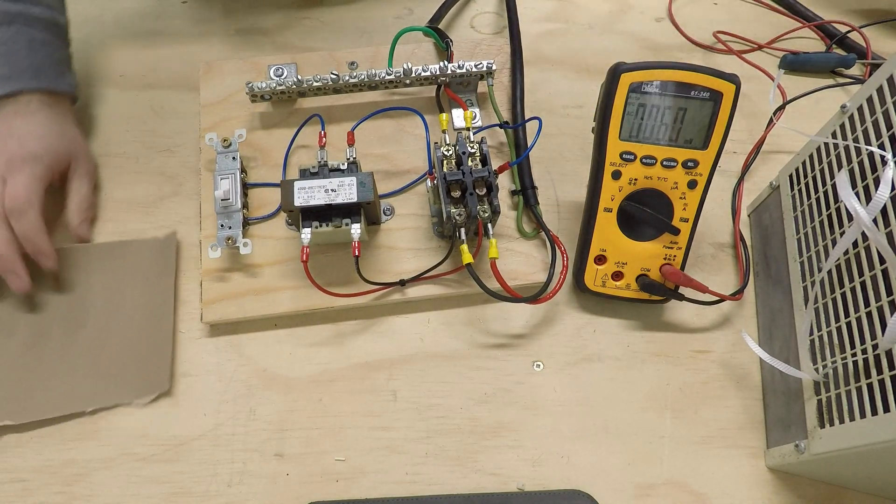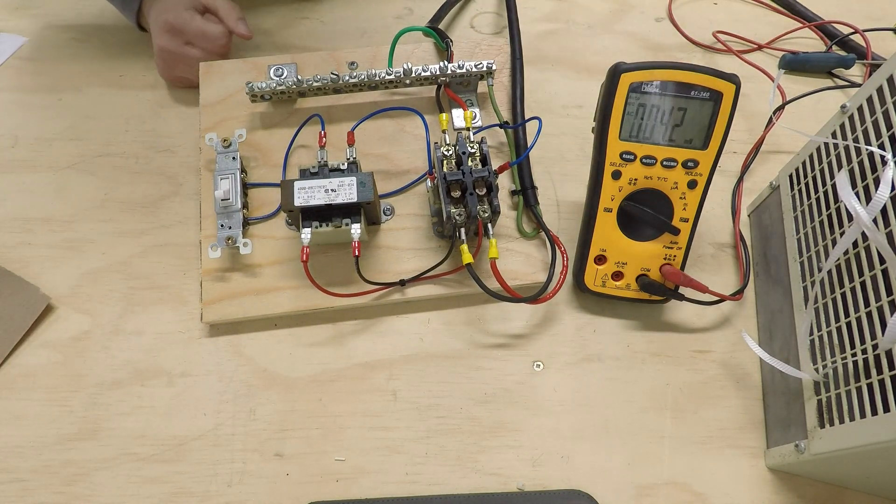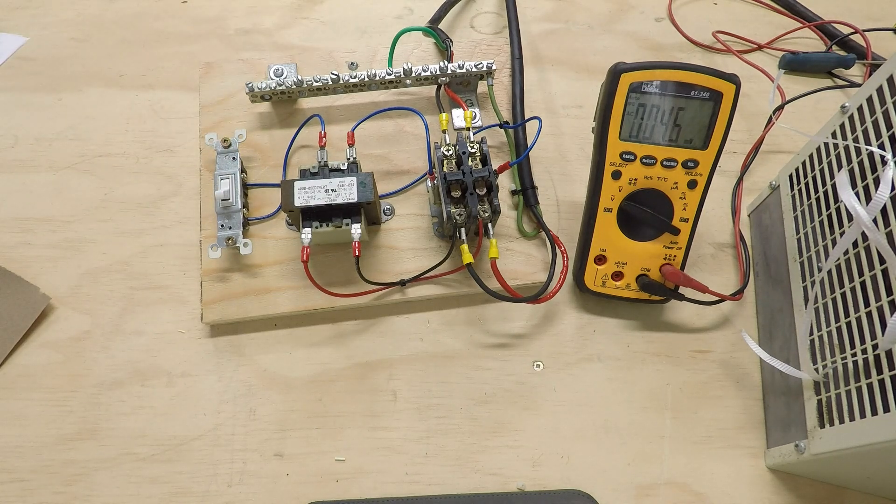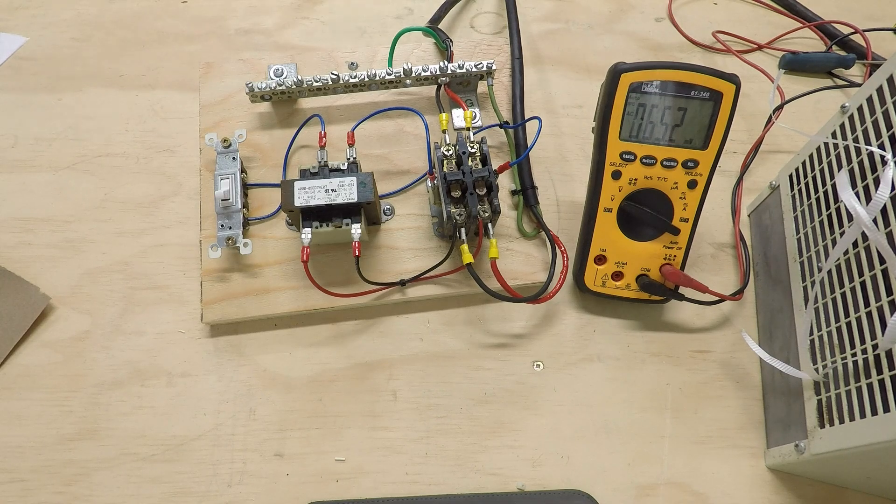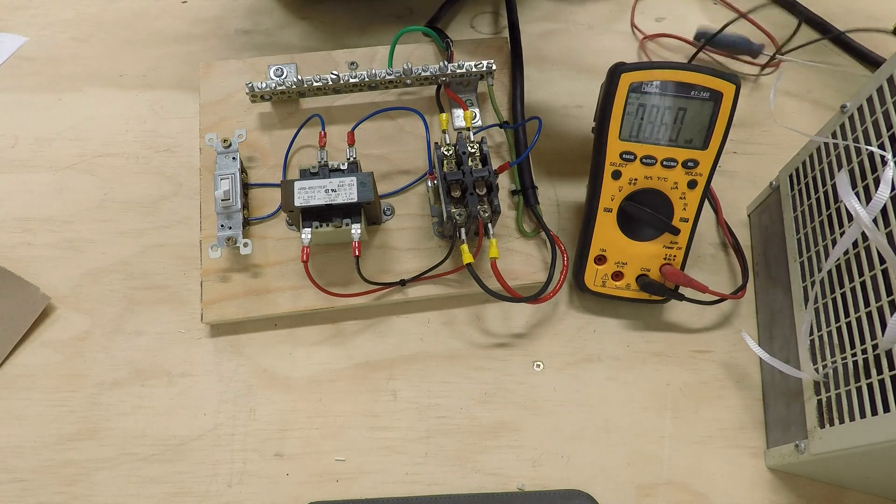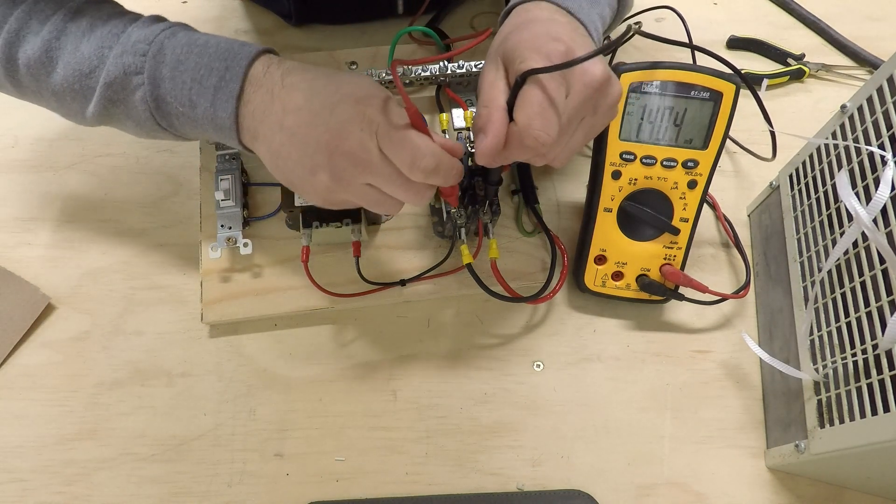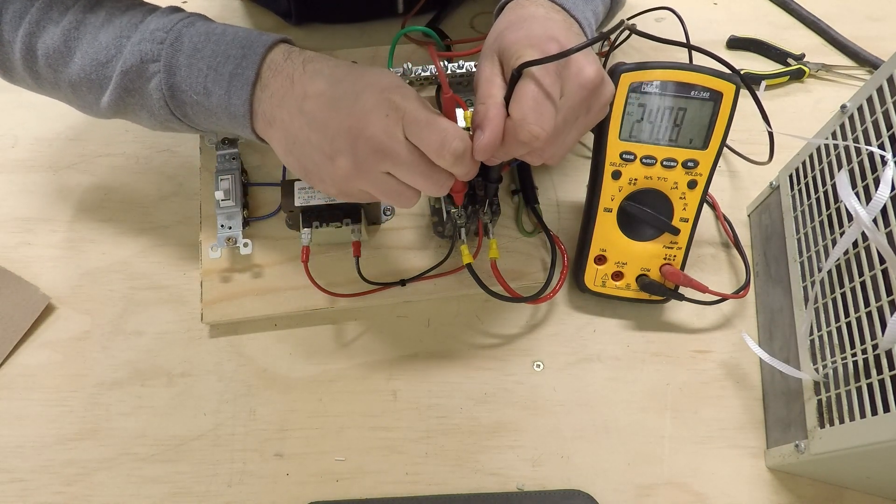So now that we've got it sanded up, my fan should turn on when I turn the breaker back on, or after I switch the switch. So I've got the breaker on now, and just to confirm, let's take a voltage measurement from phase to phase, and we've got 240 volts.